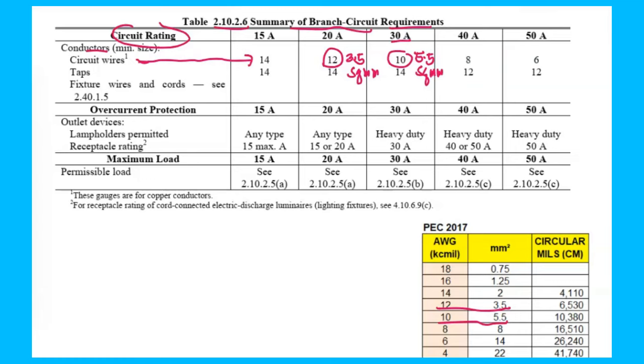So meron tayong 50, so sa 50 ampere trip daw ang gamitin mong wire, ang circuit wires is number 6. So yung ating number 6 is 14 square mm. So let's use this selected wires para dun sa aircon unit natin. Okay, malinaw to. So ang sabi, kung 20 ampere trip dapat number 12 or 3.5, pag 30 ampere trip dapat number 10 or 5.5, pag 50 ampere trip dapat number 6 or 14 square mm. So let's use this data para mag-select dun sa wires natin.